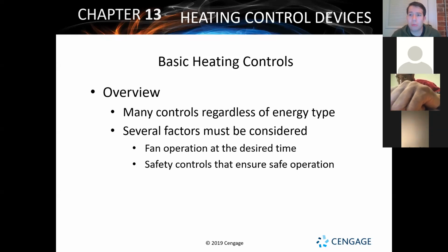Again, those kinds of controls, the blower motors, they'll have it where this allows for the fan to be in multiple speeds based on what kind of heating or cooling system it's doing. You know, is it in heat mode? Is it in cooling mode? And then also it will allow for your heating medium to actually heat up before the blower fan comes on. You know, because if a heat exchanger starts heating up and starts burning fuel, and that blower fan comes on right away, it'll actually cool it off, and you won't get any heat moving out through the building or through the structure.